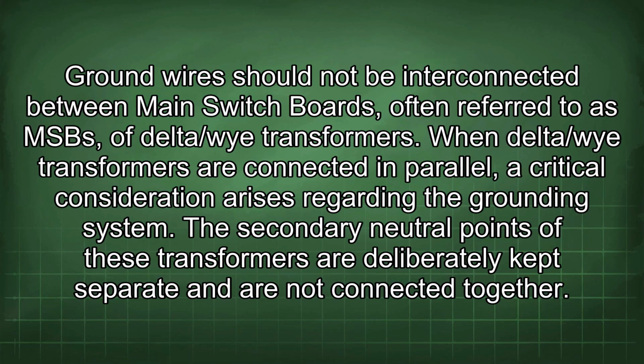Ground wires should not be interconnected between main switchboards, often referred to as MSB, of delta/Y transformers. When delta/Y transformers are connected in parallel, a critical consideration arises regarding the grounding system. The secondary neutral points of these transformers are deliberately kept separate and are not connected together.